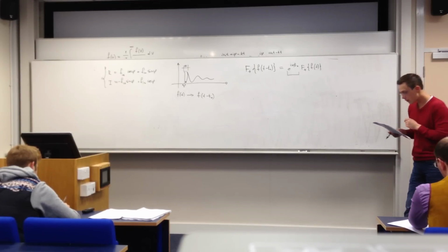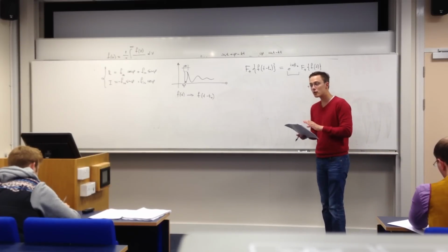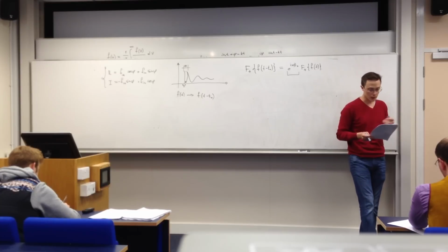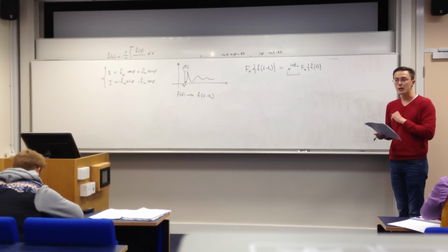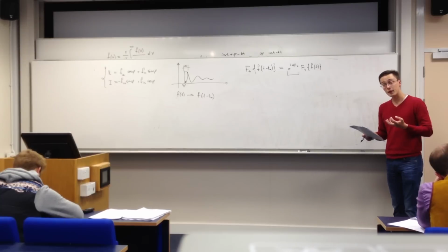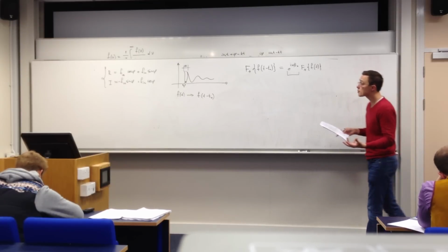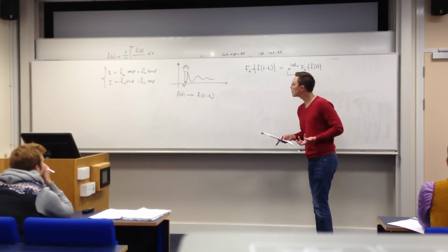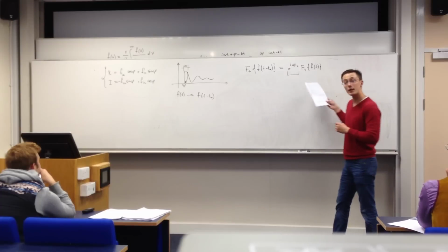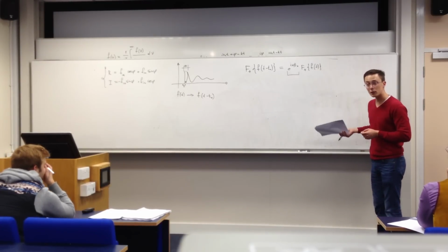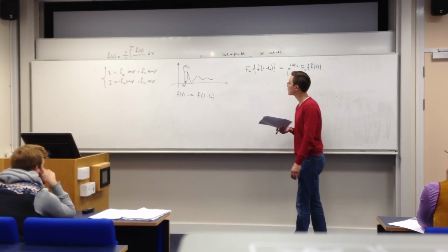If you look at the top spectrum in figure 2, it is correctly phased. Every signal is a neat peak. The middle trace is a uniform phase distortion across the entire spectrum, the same everywhere. The bottom trace is an example of a linear phase distortion, with different values of the complex phase at different parts of the spectrum. When you do this on a spectrometer, particularly for things like carbon and fluorine spectroscopy, you will necessarily find that you have this linear phase correction, and you have to account for it. It's inevitable, it's natural, it's just a consequence of this little delta. So it's not something to be worried about.